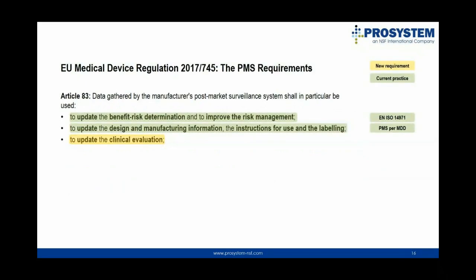So, with Article 83, some entirely new requirements for PMS are being introduced when compared to the MDD, and no guidance so far has covered PMS in this level of detail. The green highlights indicate requirements that can be found in recent standards or guidance documents. Yellow highlights indicate new requirements. The ISO 14971:2012, for example, requires manufacturers to use post-production experience to improve the risk management. Also, as already mentioned, post-production experience should be used to update the design and other information. One of the most crucial interfaces that is new is the requirement to update the clinical evaluation with post-market experience data, as expressed by my colleague Oliver.